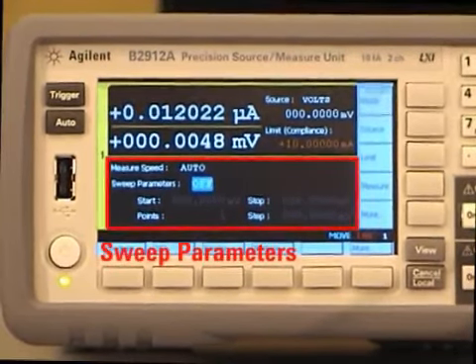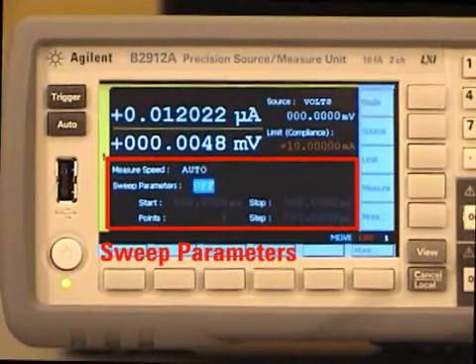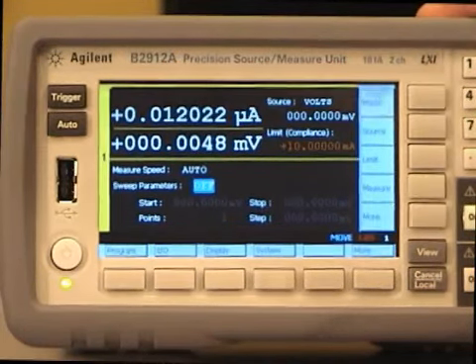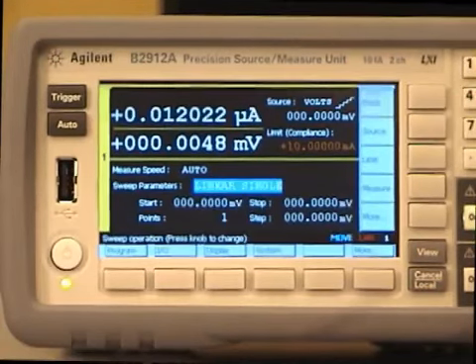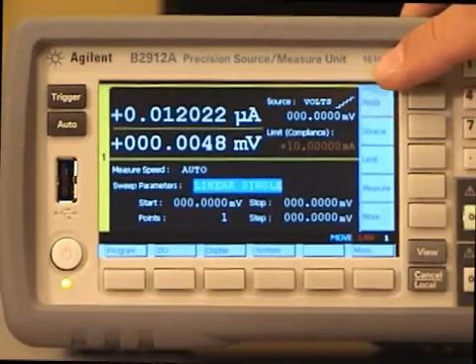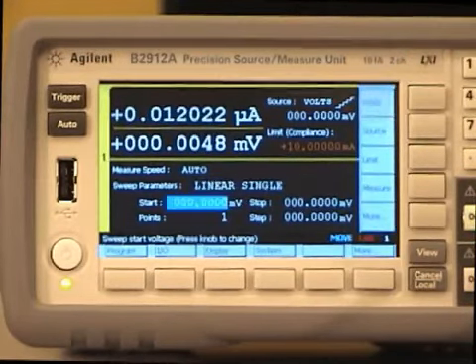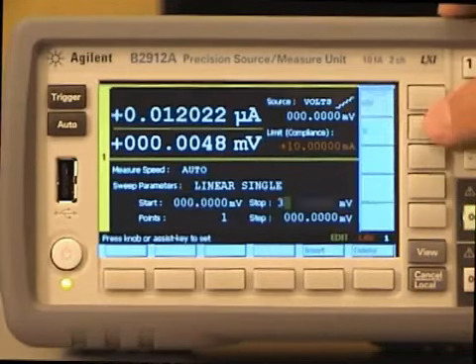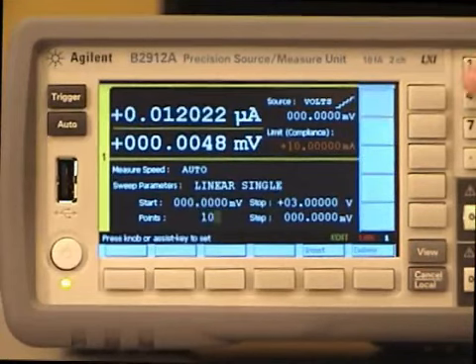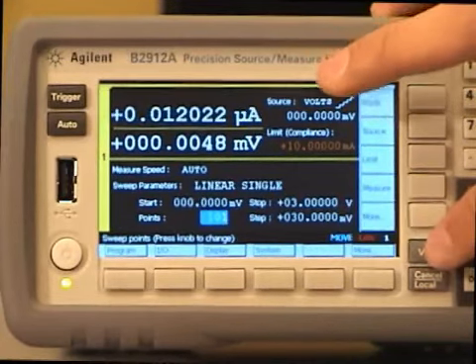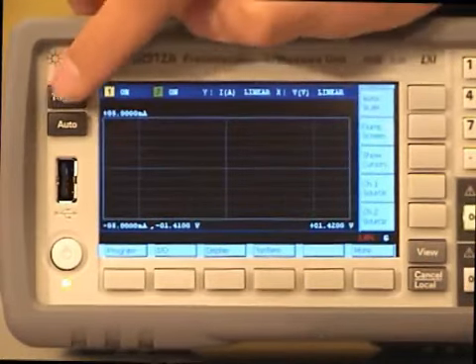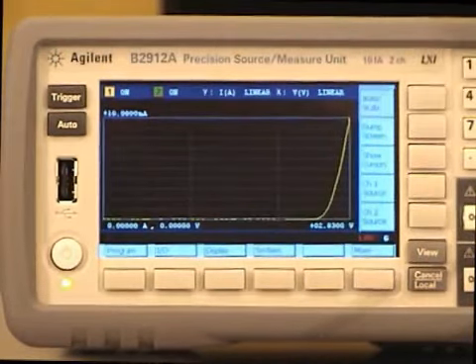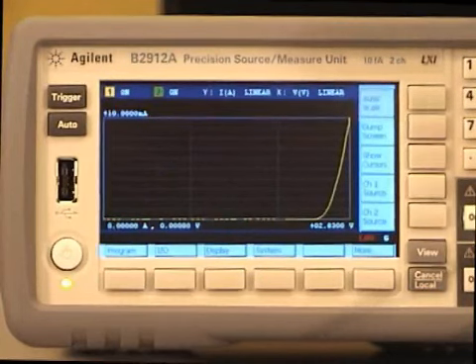Next, I will demonstrate how easy it is to perform an IV sweep measurement. Here is the sweep parameter area. You can set all sweep parameters here. First, set the sweep parameters to linear single. Then, you can find the staircase symbol here. Set the start voltage to 0, stop voltage to 3V, and the number of points to 101. Change the view to graph view. Press the trigger. Apply the auto scale. And you can see the IV characteristics of the LED here.